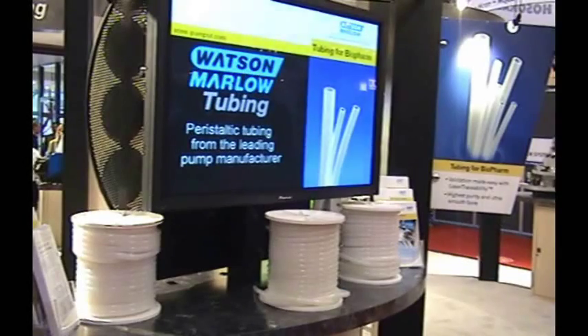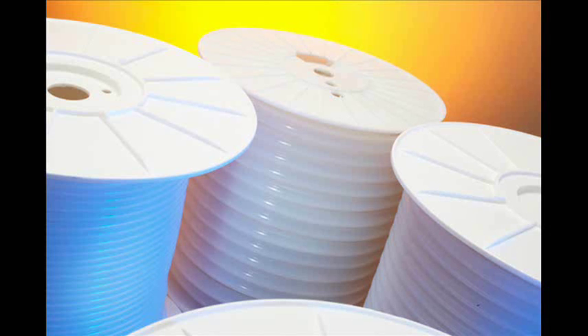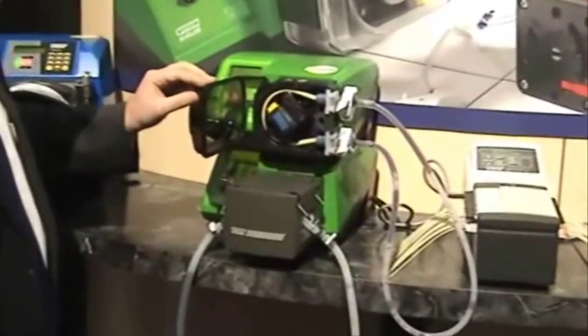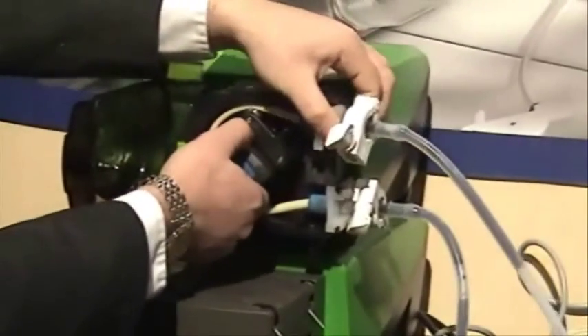When the tubing is all that touches your fluid, purity is paramount, which is why Watson-Marlow extrudes its own BioPharm-grade tubing. Our Pumpsil platinum-cured silicone is post-cured to drive off cytotoxic extractables that many tubing manufacturers actually overlook. We also manufacture long-life bioprene thermoplastic tubing and our newest weldable tubing, PureWeld. Changing this high-purity tubing completely replaces your fluid path, significantly simplifying cleaning validation.